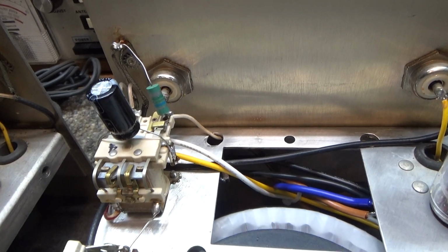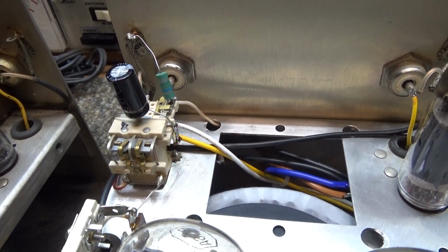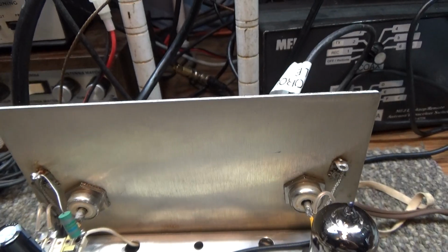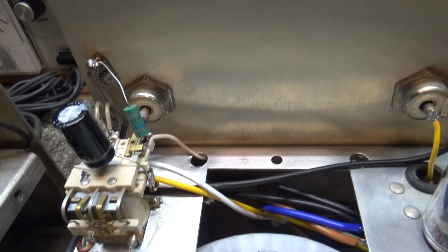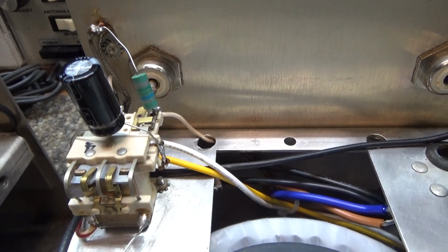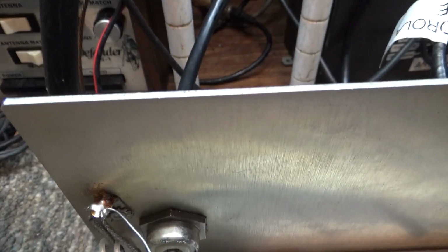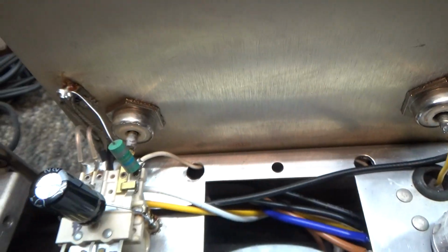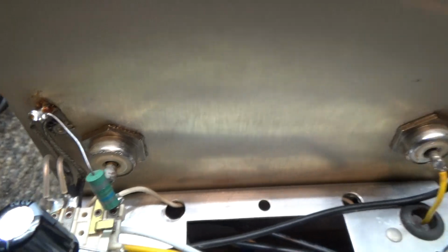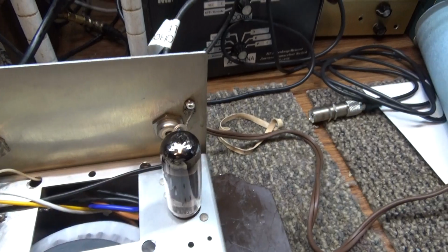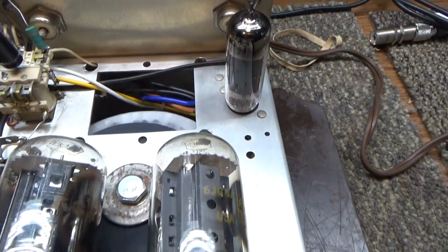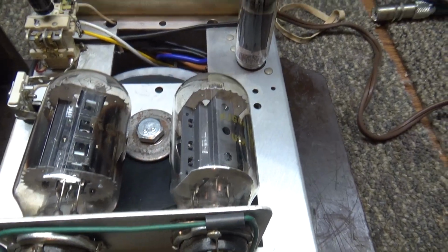That relay is connected to the center tap of the high voltage. So if you need to replace it, it's 120 volt DC, and if you notice, it's just a 2-pin or 2-pole relay. All it has is in and out - RF in on one pole and RF out on the other. There's no contacts for switching to turn on the transformer or bias for the grids or tubes or anything like that.